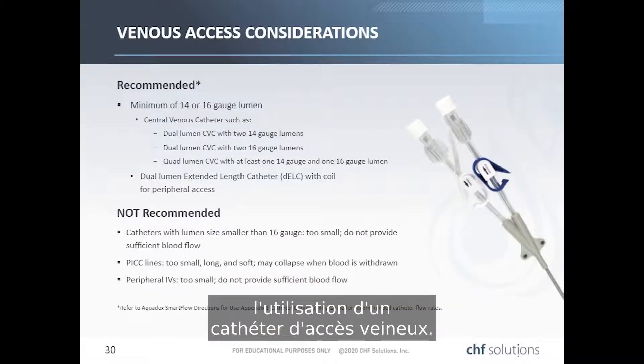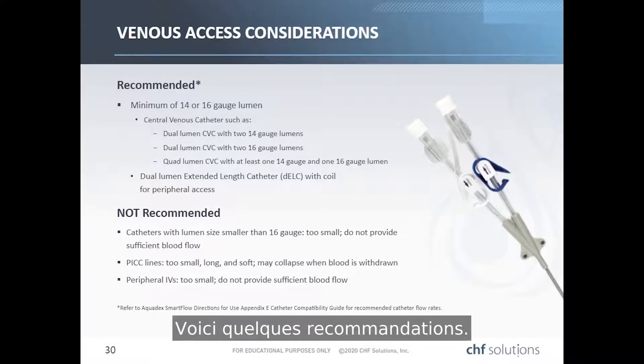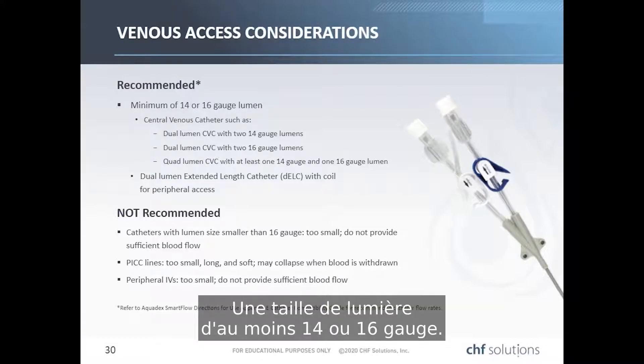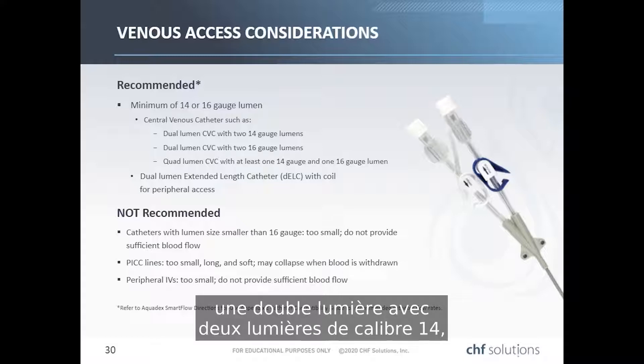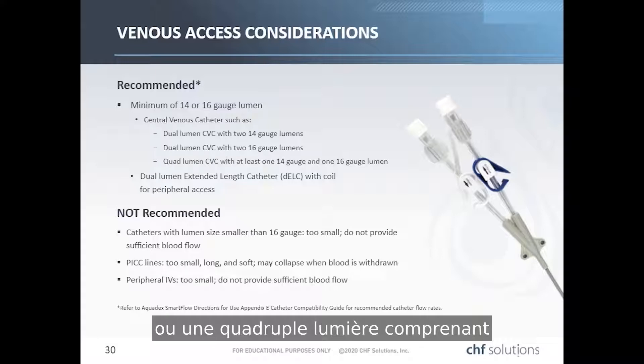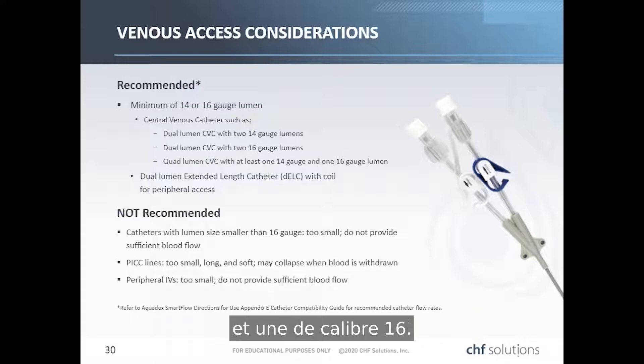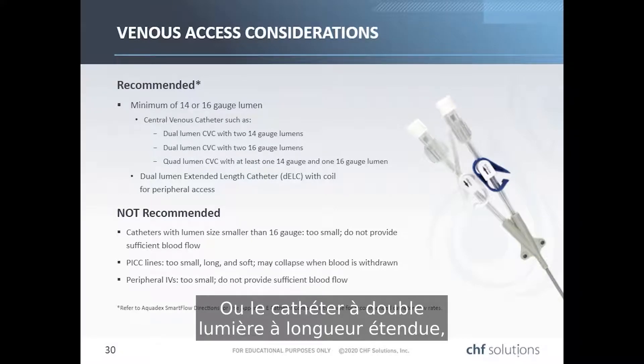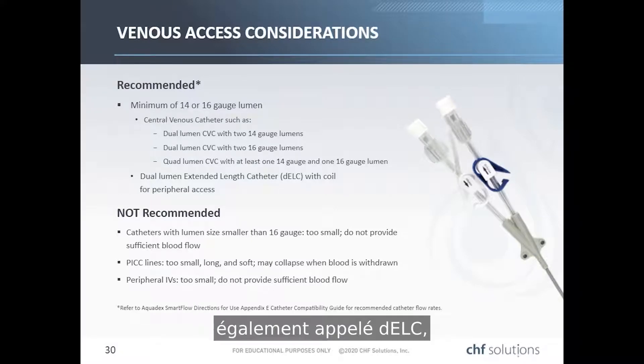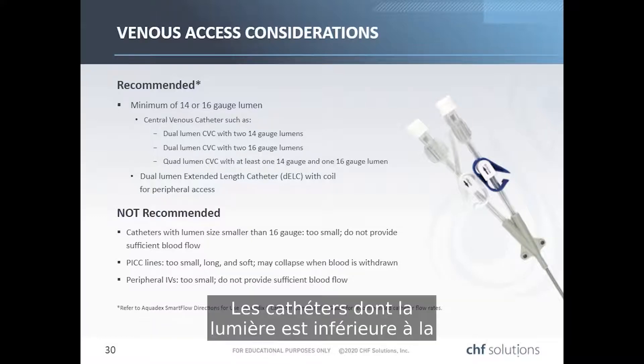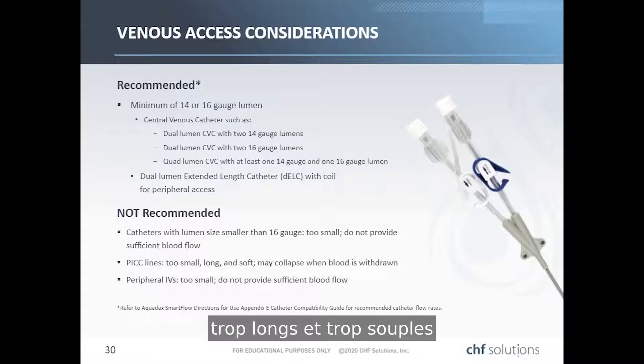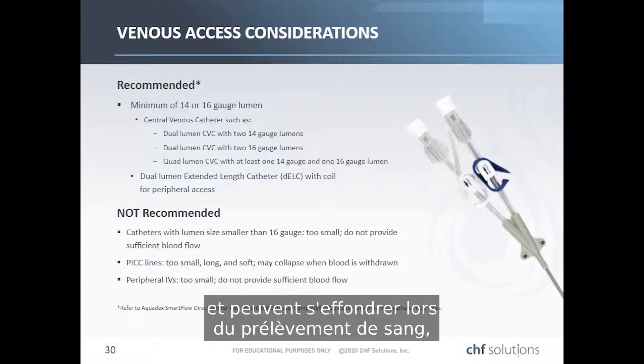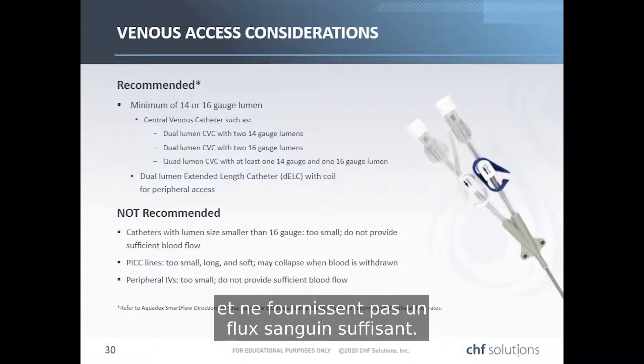Aquadex therapy requires a venous access catheter with a minimum of 14 or 16 gauge lumen size. For central venous catheters, options include a dual lumen with two 14 gauge lumens, a dual lumen with two 16 gauge lumens, a quad lumen including at least one 14 gauge and one 16 gauge lumen, or the dual lumen extended length catheter (DELC) with a coil for peripheral access. Not recommended are catheters smaller than 16 gauge, PICC lines (too small, long, and soft), or peripheral IVs, which do not provide sufficient blood flow.